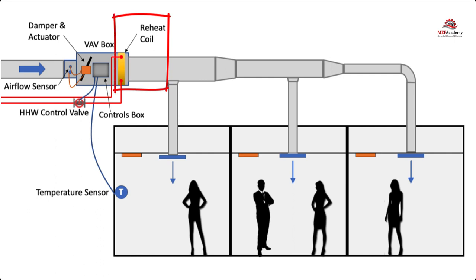There is a reheat coil depending on the zone. Most exterior zones will have a reheat coil; a lot of interior zones won't unless you're in a hospital or some other special space. The reheat coil provides heating either through heating hot water, steam, or electric. The use of electric is limited in some jurisdictions due to energy codes.